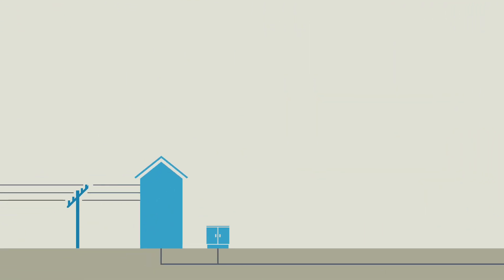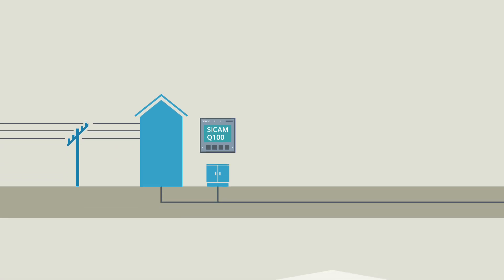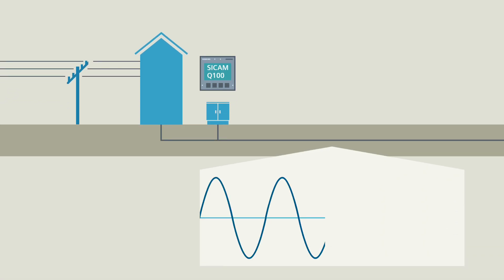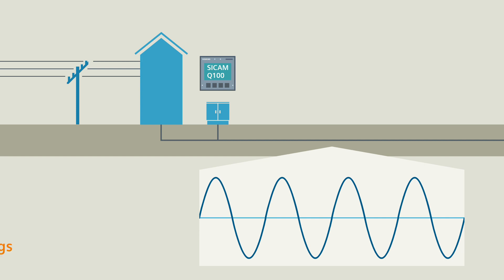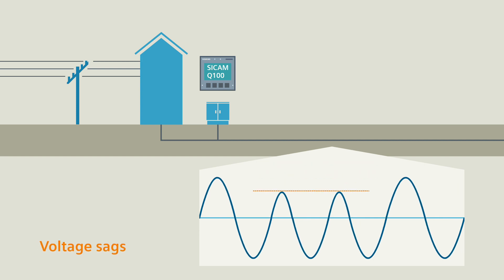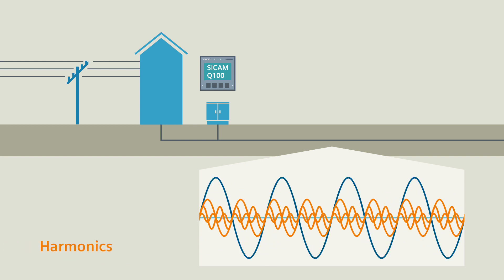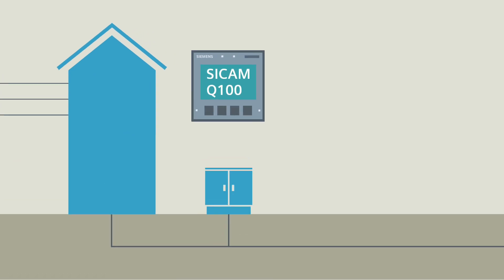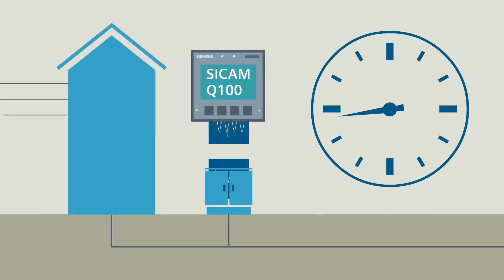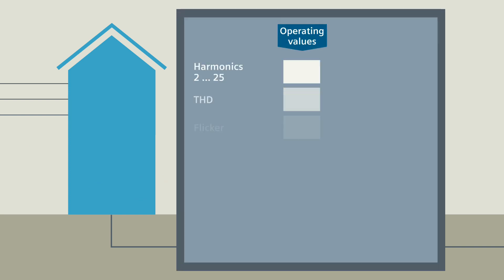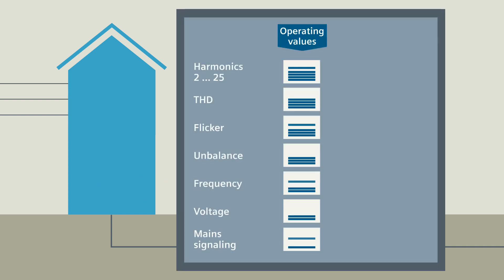As an example, let's take a typical secondary substation that is monitored by a SICAM Q100. In the line, voltage-related interferences can occur all the time — for example, voltage sags, transients, harmonics, and much more. The SICAM Q100 constantly records these interferences and saves the individual operating values separately for each measured quantity.